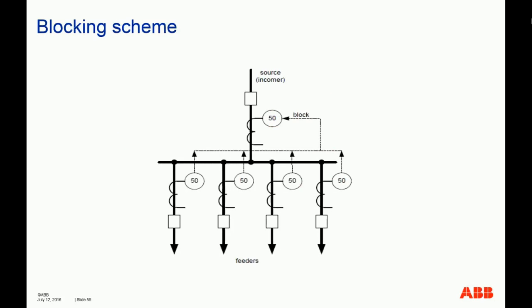This type of blocking scheme requires a certain type of communication. The idea is that sometimes it is economically not justified or not necessary to put in a dedicated bus bar protection. So how are you going to protect the bus, right? You have the main incomer relay, you have a feeder relay. So the only way is for the two groups of relays to communicate with each other. Traditionally, you use wires.